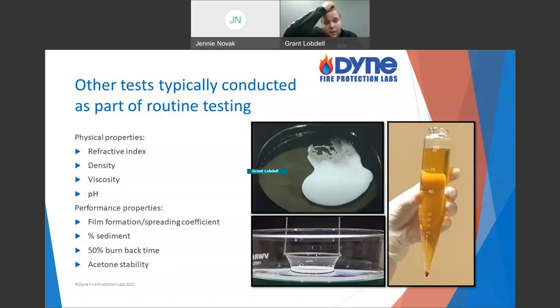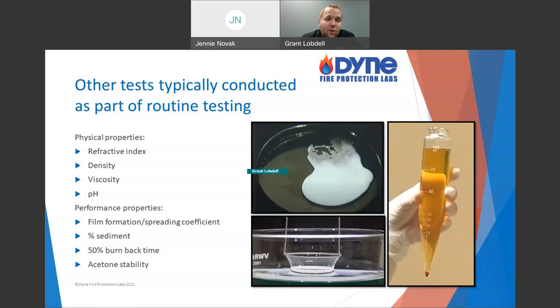Film-forming foams are obviously under some scrutiny. To get this film, you need a very low surface tension or a very positive spreading coefficient. To achieve that, unfortunately, you do need fluorochemicals — at least to date. I'm not aware of any non-fluorochemical-based surfactants that will achieve a low enough surface tension to form a film. This does rule out our synthetic fluorine-free foams (SFFFs), which aren't going to form a film.